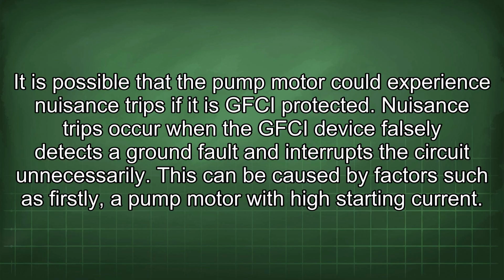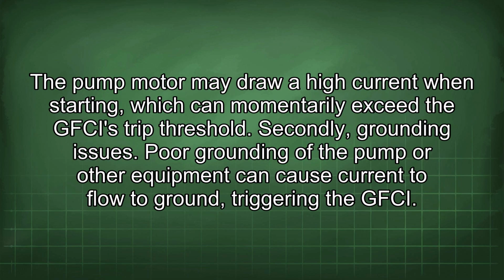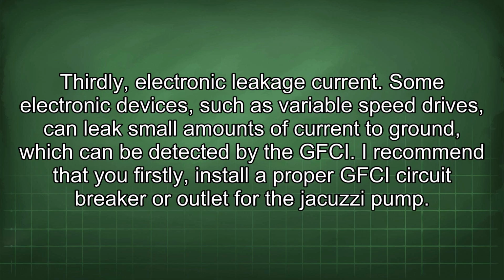This can be caused by factors such as, firstly, a pump motor with high starting current. The pump motor may draw high current when starting, which can momentarily exceed the GFCI's trip threshold. Secondly, grounding issues. Poor grounding of the pump or other equipment can cause current to flow to ground, triggering the GFCI. Thirdly, electronic leakage current. Some electronic devices, such as variable speed drives, can leak small amounts of current to ground, which can be detected by the GFCI.